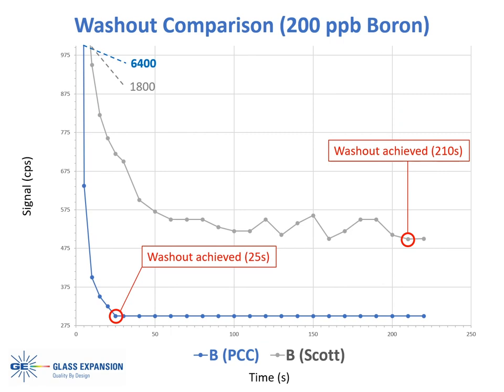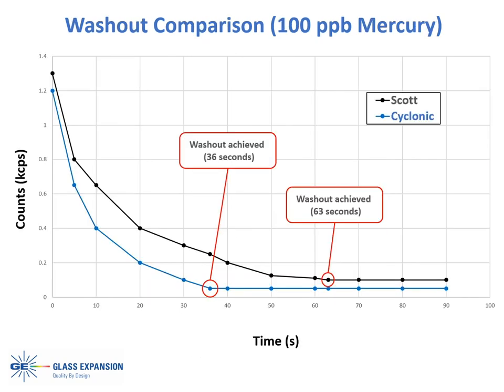Here we compared the washout efficiency of our PCC kit to a Scott-style spray chamber. The same 200 ppb sample was aspirated until the signal stabilized, followed by the rinse solution; timing began as soon as the rinse solution was introduced. The boron signal with the PCC kit started out three times higher than the Scott but achieved a washout time eight and a half times faster and returned to a lower signal than the Scott. A second washout comparison using a 100 ppb mercury solution showed mercury washed out nearly twice as fast with the PCC kit as it did with the Scott-style spray chamber.